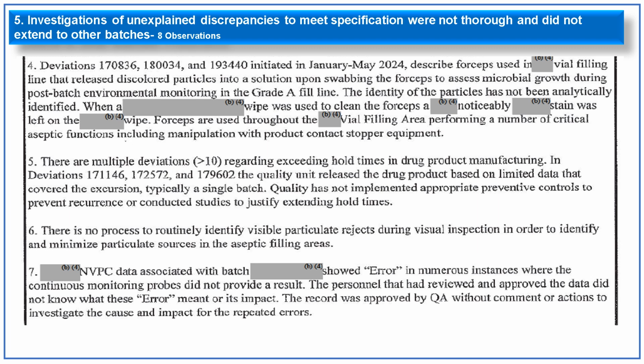The fifth point is there are more than 10 deviations regarding exceeding of hold times in the product manufacturing. In 3 of the deviations, the quality unit released the product based on limited data that covered the excursion, typically a single batch. So the quality unit has not implemented appropriate preventive controls to prevent recurrence or conducted studies to justify extending hold times. The sixth point is there is no process to routinely identify visible particle rejects during visual inspection in order to identify and minimize particulate sources in the filling aseptic areas.